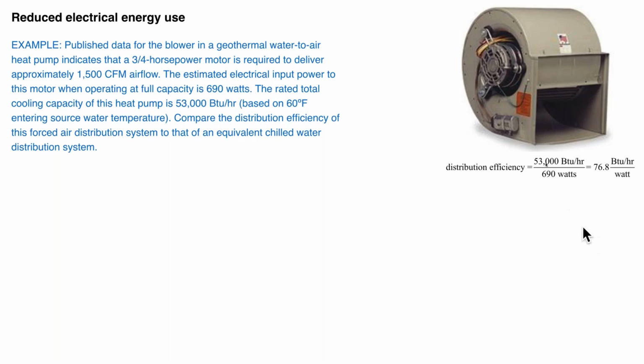We just take the rate of cooling delivery, 53,000 BTUs per hour, divide it by the power going in to operate the motor on the blower. In this case, based on manufacturer's literature, 690 watts. So we get this number. Interpreting this number, for each watt of electrical power fed to that blower, it's delivering, I'll round it off, about 77 BTUs per hour of cooling.